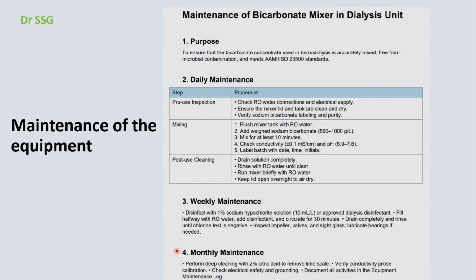So lots is wasted. Just as I said, the maintenance of the equipment is more important, and before starting the use, you have to inspect the tank. And as earlier said, it should have a supply of RO and drainage itself, and should have good ventilation. So after you have inspected the machine, you fill the tank with the RO and add the recommended dose of the dry bicarbonate. And then it is constantly agitated to prepare a standardized solution. After use also, it has to be thoroughly rinsed and dried off to prevent any precipitate formation on it. So it requires a weekly maintenance and daily checks.